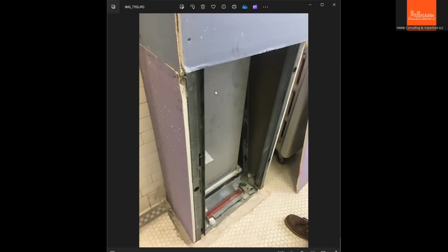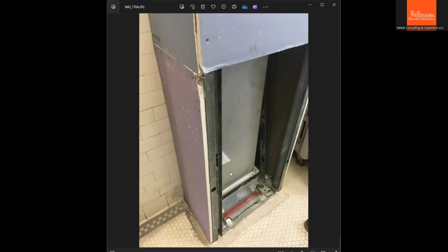So we can say this is a ductwork. We could also keep as an example, like this duct is like the column that needs to be protected from fire condition, or needs to have a fire rated enclosure like this. So that's the recommendation that I have discussed with them, but still it's up to the designer of the building or the engineer or the architect to have it approved, because if they're spending too much money on the intumescent paint, this is one alternative that is much simpler to install. And much faster.